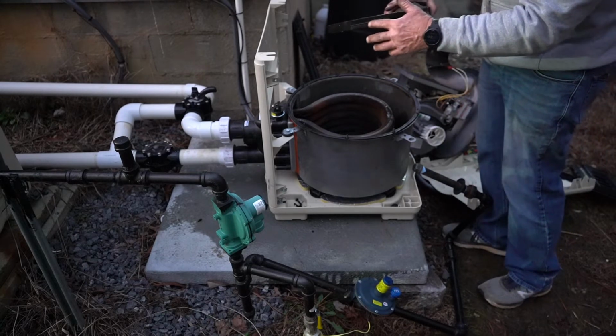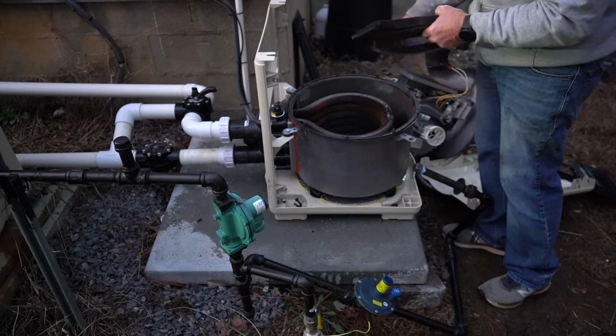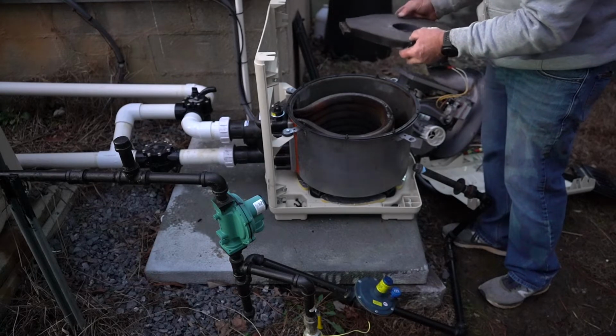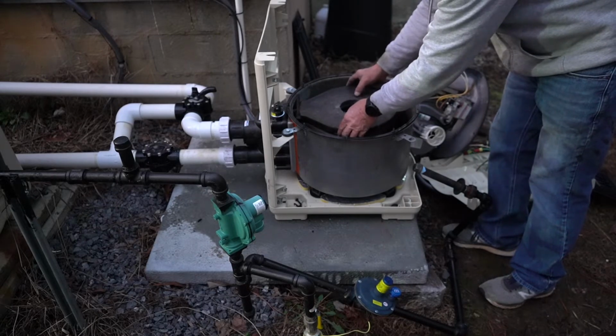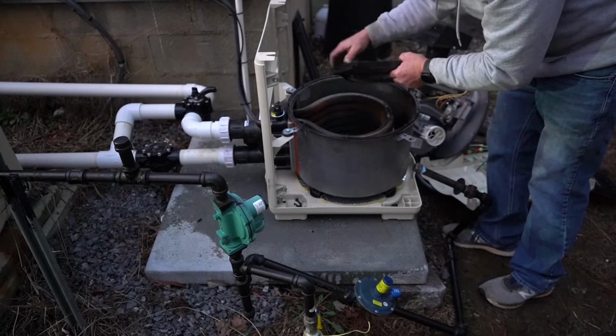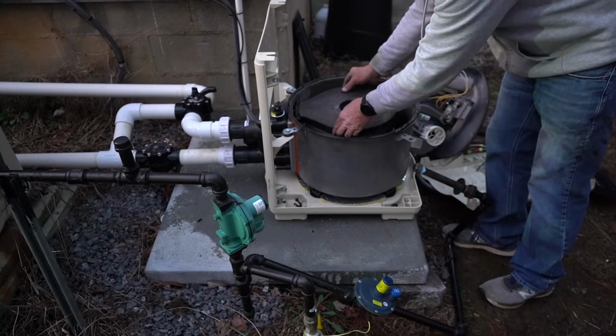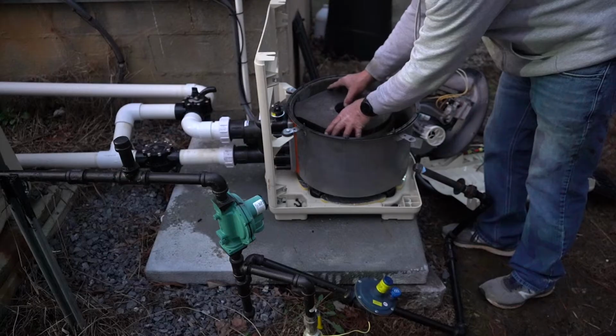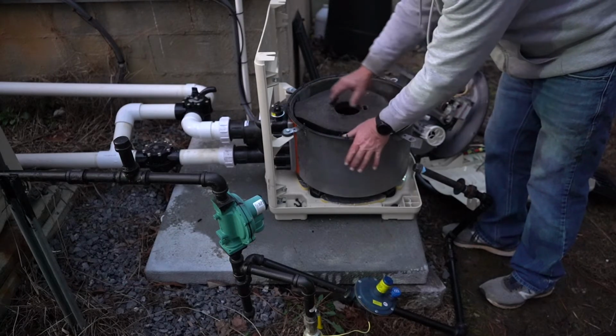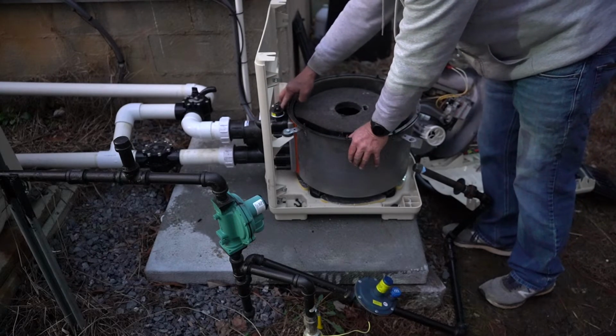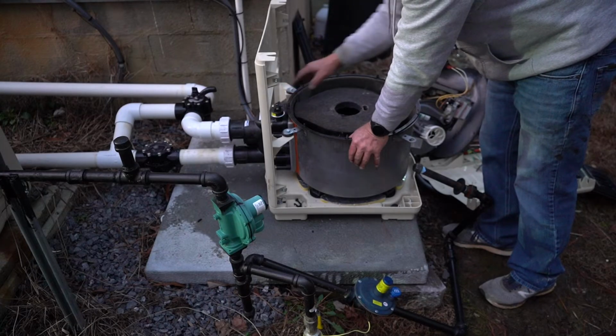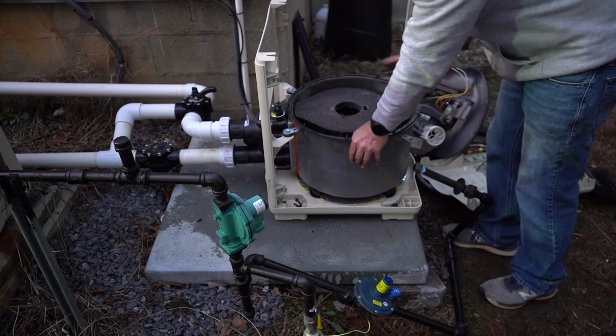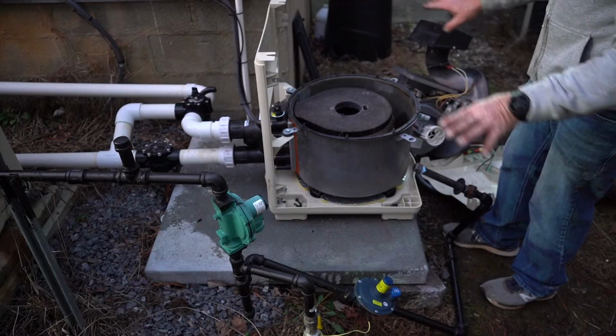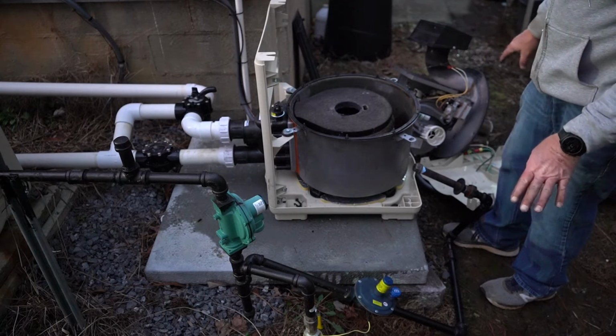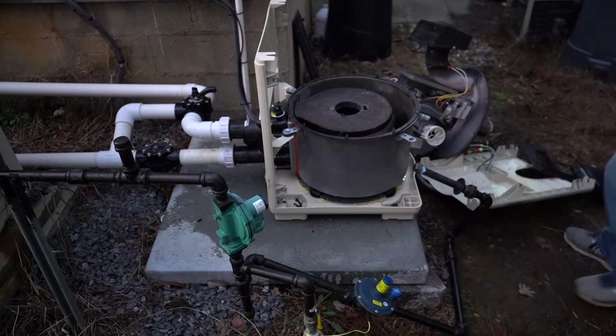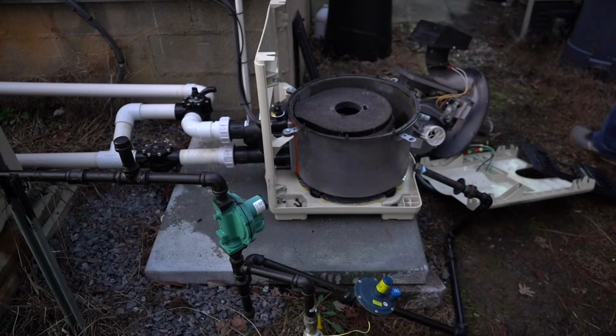Now we have this lip on the top piece, which is our fire block, and we want to make sure we don't lose that lip, because if it cracks off, the heat will get out to this I/O header and melt it, and it'll start to leak. Then you'll have to take this whole thing apart, put new fire blocks in, and start again. So be very cautious of that.